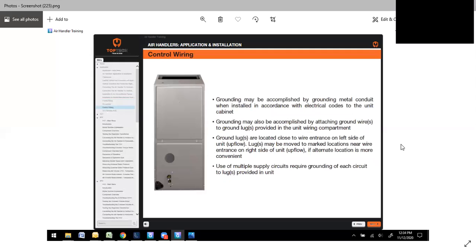Grounding may be accomplished by grounding metal conduit when installed in accordance with electrical codes to the unit cabinet. Grounding may also be accomplished by attaching ground wires to ground lugs provided in the unit wiring compartment. Ground lugs are located close to the wire entrance on the left side upflow. Lugs may be moved to marked locations near wire entrance on the right or upflow if alternate connection is needed. Use of multiple supply circuits requires grounding of each circuit to the unit. So if you have 2 power wires coming here, you've got to make sure that you actually ground both those circuits.